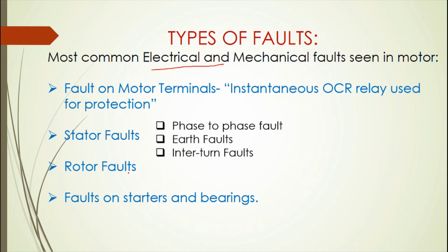Rotor faults. Such faults are more likely to occur in wound rotor motors. The thermal and mechanical stress produced due to rotor faults leads to rotor bars being cracked, and there is also a possibility of the rotor getting damaged, due to which the torque of the motor gets reduced. Fault on starters and bearings. Mechanical imperfections such as misalignment of rotor or rotor unbalance or failure in the bearings can lead to faults on starters and bearings.